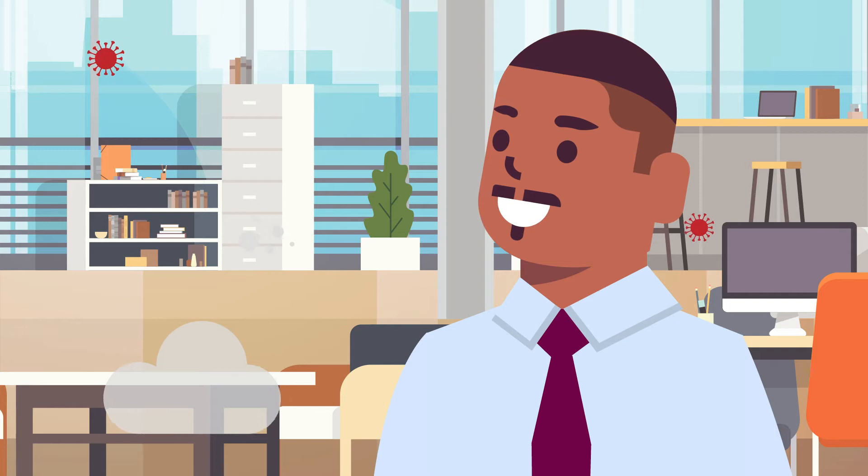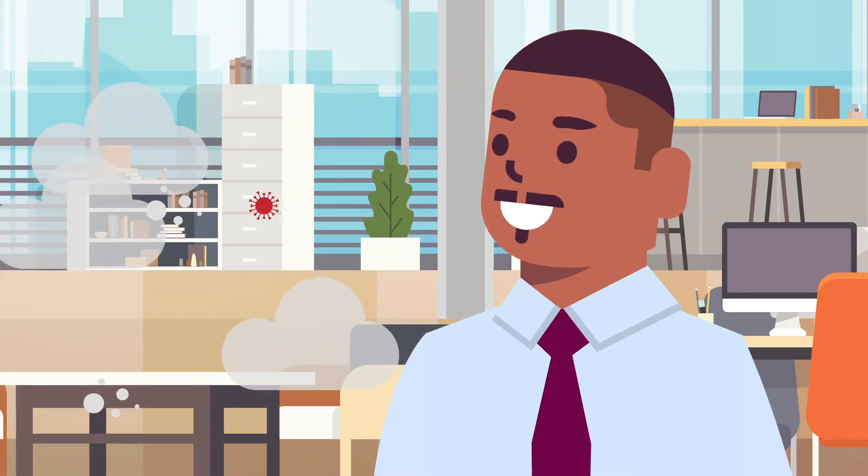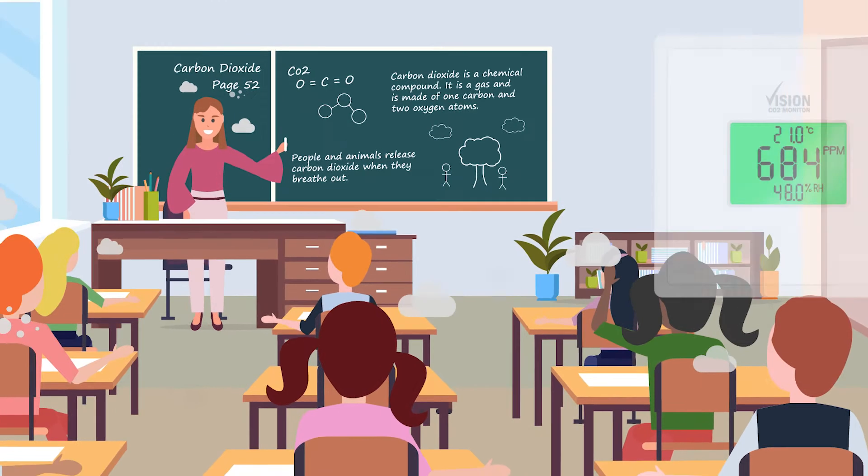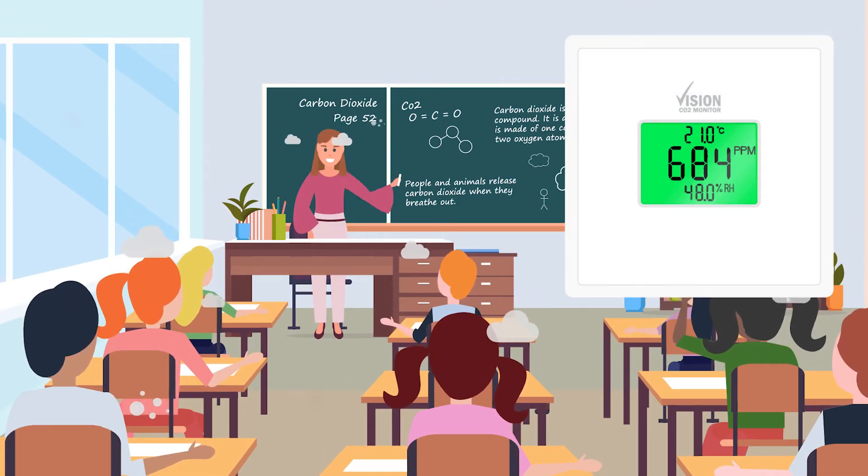It is for this reason that CO2 can be used as a general indicator for proper ventilation in occupied indoor spaces such as classrooms and offices. If there are elevated CO2 levels, this means that the air we are breathing out is not being removed, which could contain other contaminants or even viruses. Whether or not these particles are being removed can be measured using a CO2 monitor.